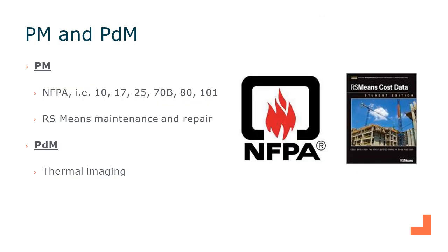We've set up our PMs and our preventive and predictive maintenance based on guidelines from NFPA, RS Means, ASHRAE, as well as other organizations that have recommendations and standards used for that. NFPA is typically adopted in our area as code, so it goes from being a recommendation to being a requirement.